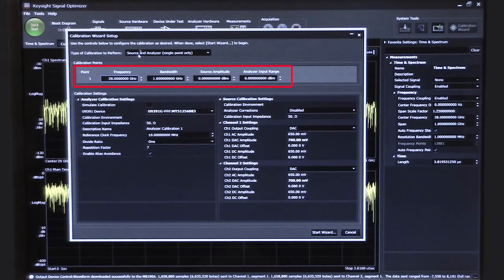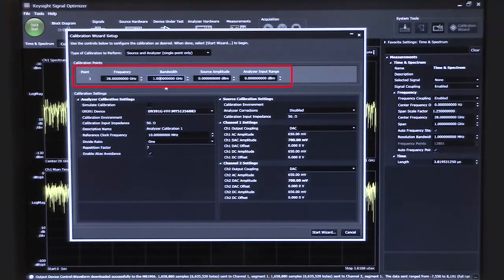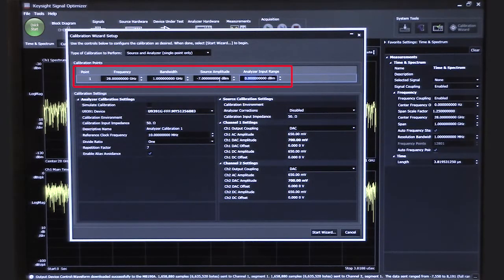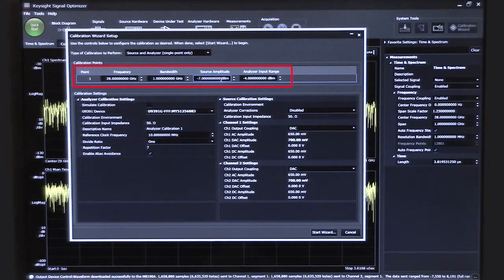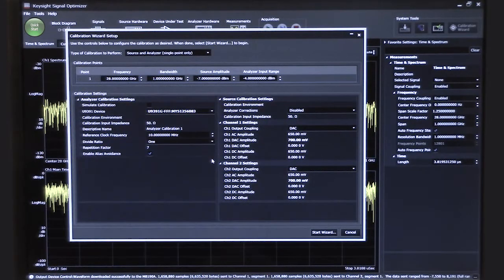In this example, we're going to do the full source-analyzer calibration. At the top here we can set the frequency, and in this example we want to use a frequency of 28 GHz. So I've set that to 28 GHz. We're going to calibrate over the full bandwidth of the measurement system — in this case, 1 GHz. We're going to set the source amplitude to minus 7 dBm, and then we'll set the analyzer input range to about minus 4 dBm, which we determined earlier was the right range for the cable loss we have at 28 GHz.